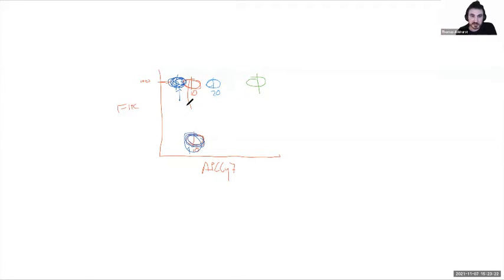If the batch of beads is different, or if you're using a combination of beads and cells, it's possible that fixing beads may increase the inherent autofluorescence. I don't know if that's actually true, but if for instance these for whatever reason were fixed and these weren't, say someone missed a well, it's plausible that that could do that as well. Now, the way fixation works shouldn't do that to beads, but it's entirely plausible that somehow something is changed by that treatment. So it's fundamentally going to be a problem of mismatching the autofluorescence between whatever these events are and whatever these events are. That's what causes it.